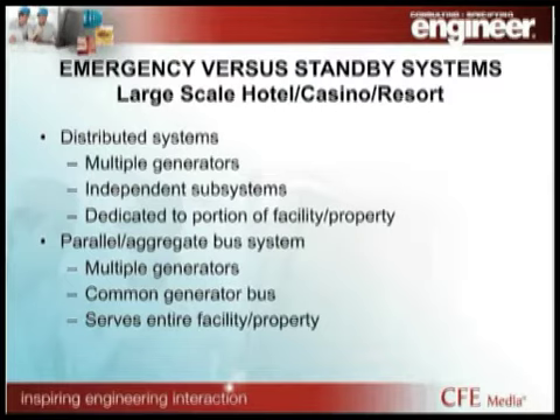So what type of systems do you use? Obviously, discussing all the different alternatives and options is beyond the scope of the time frame we have today. But really there's two ways to look at it. There's distributed systems, particularly when you're talking about a property that may be anywhere from 5 to 10 million square feet all in. You can do that with multiple generators and independent subsystems, and it's typically the generator then is tied to a specific portion of the facility. It's also going to be set up with transfer switches for the emergency, legally required, and critical or optional standby that basically define those subsystems within the zone of the building it serves. Some of the advantages or disadvantages of this type of system: if you have one generator failure, you lose a portion of the facility. One of the advantages is it's simpler.